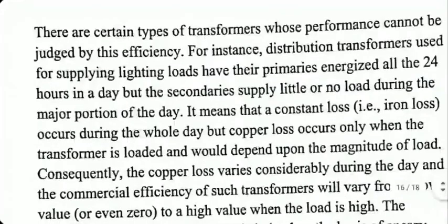It means that a constant loss, that is iron loss, occurs during the whole day. Iron loss doesn't change. It will keep occurring throughout the day, even if nothing is connected to the secondary. But copper loss occurs only when the transformer is loaded. And the copper loss would depend on the magnitude of the load, which means the magnitude of the secondary current, and power factor, of course. Actually, no, the loss will not depend on power factor, but many other things will.